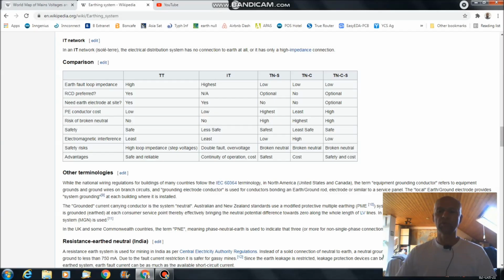So why does some code only require an earth electrode for lightning protection? That again has to do with the earthing system itself. If you live in a TT system, you see an earthing electrode there, of course you need to have one, because it's the only low impedance way for earth faults. But most of us users actually are getting their electricity from one of these 2 systems here, either a TNS or a TNCS, and there, especially at the TNS, an earthing electrode is not required at the site, because we already have a very low earth fault loop impedance there.